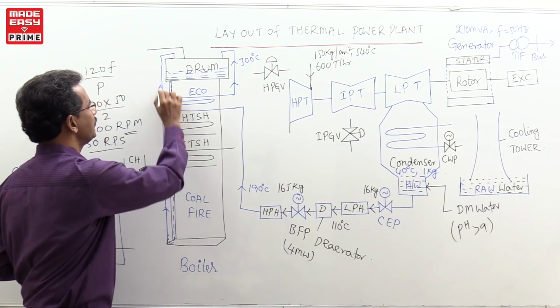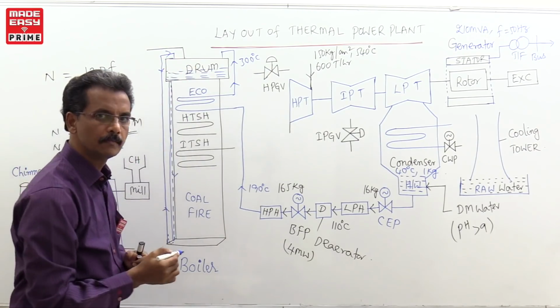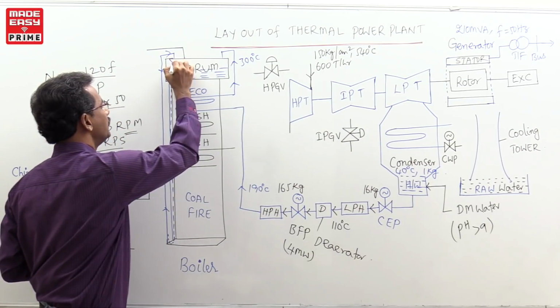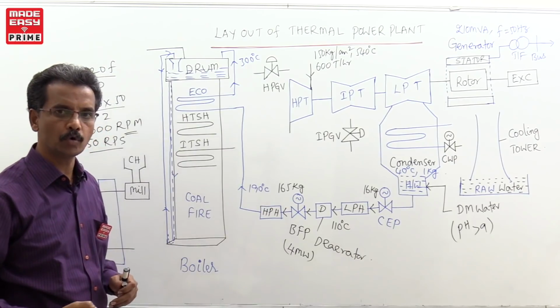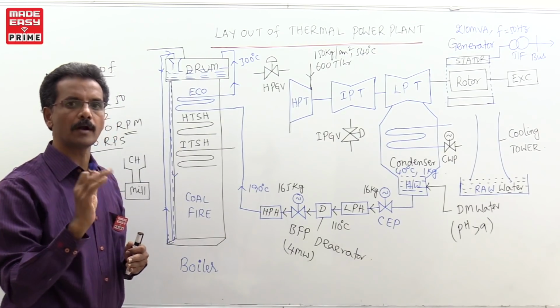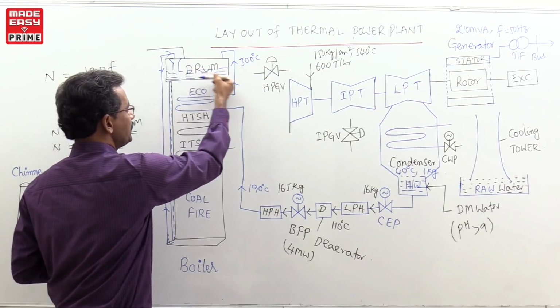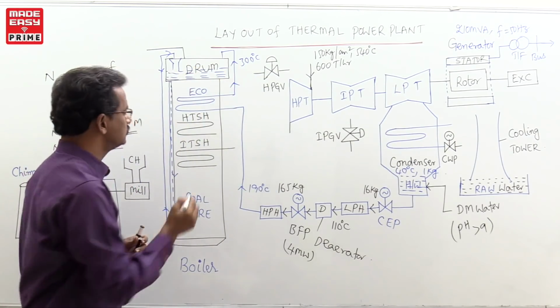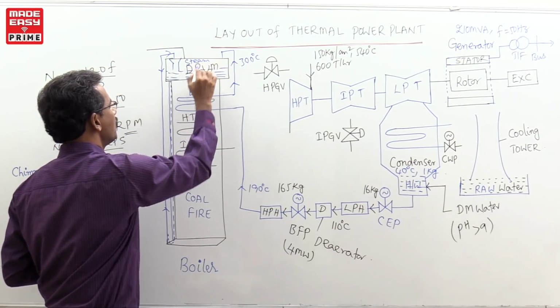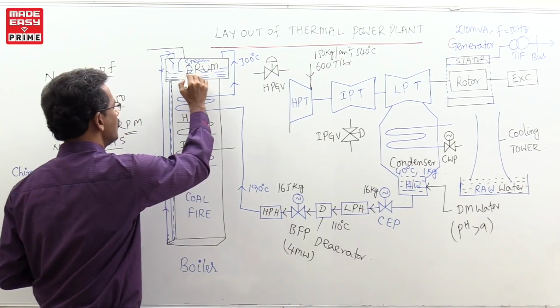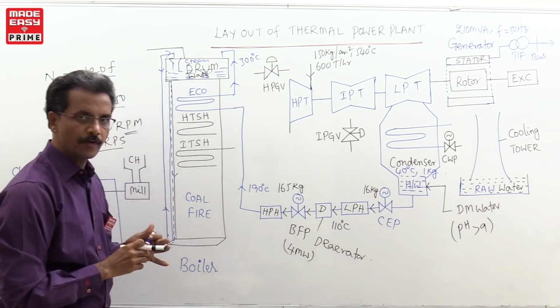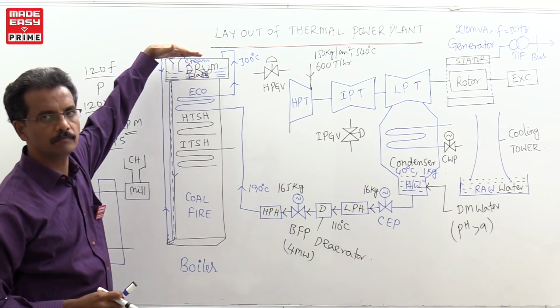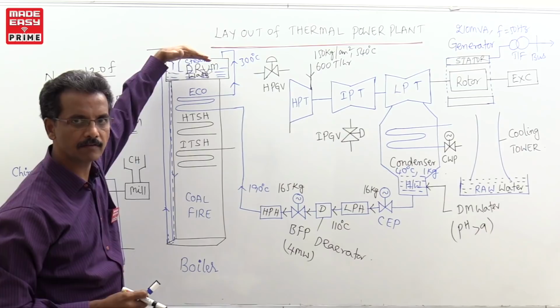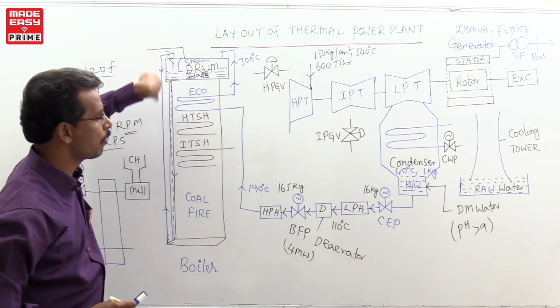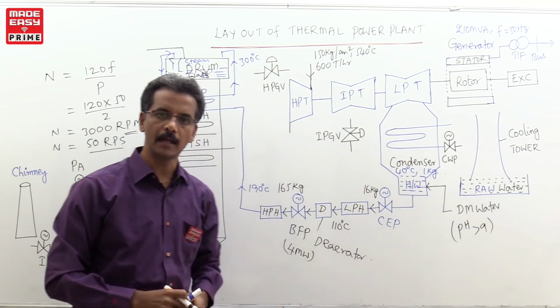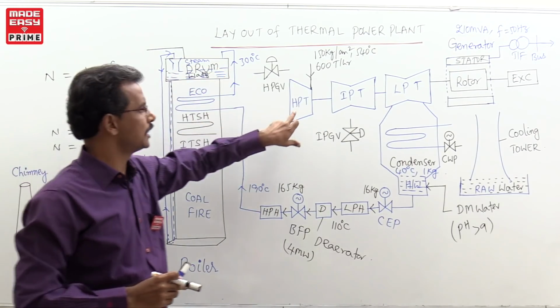Now the steam enters into the main drum. Water and steam mixture both enter into the drum, and here they use one mechanism called a turbo separator. It will separate the water and steam. Now, 50% of the drum level is normally maintained as water and 50% as steam. The big idea is, if the water level in the drum is very high, what will happen? Instead of steam, more water will enter the turbine, and the turbine blades will get damaged.